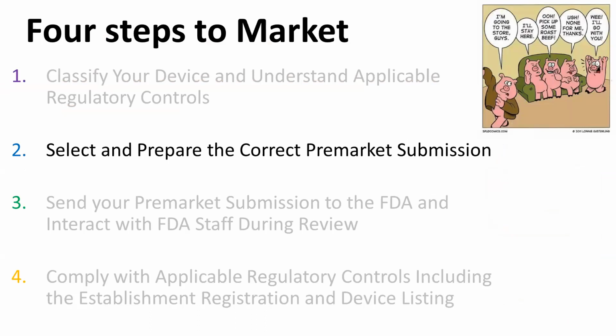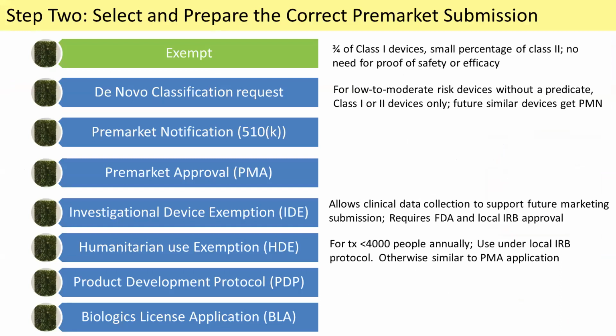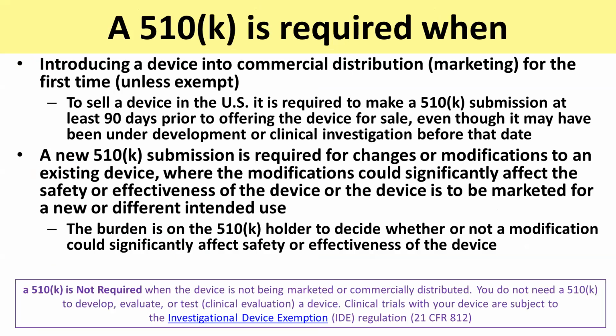So now that we've discussed the classifications, we need to prepare the correct pre-market submission. And there is, as you can see, about 8 different pathways to go down here. Now, the ones that are most applicable to us in our surgical device development are the pre-market notification, which is commonly known as the 510K, and the PMA, the pre-market approval. For class 1 devices, if you make an instrument, you might be exempt if it's low risk. If you need to gather data for your device, you might need to do an investigational device exemption where both the FDA and the local IRB approve. So there's a whole bunch of different classes, but we're going to focus on the 510K and the PMA because that's the most common.